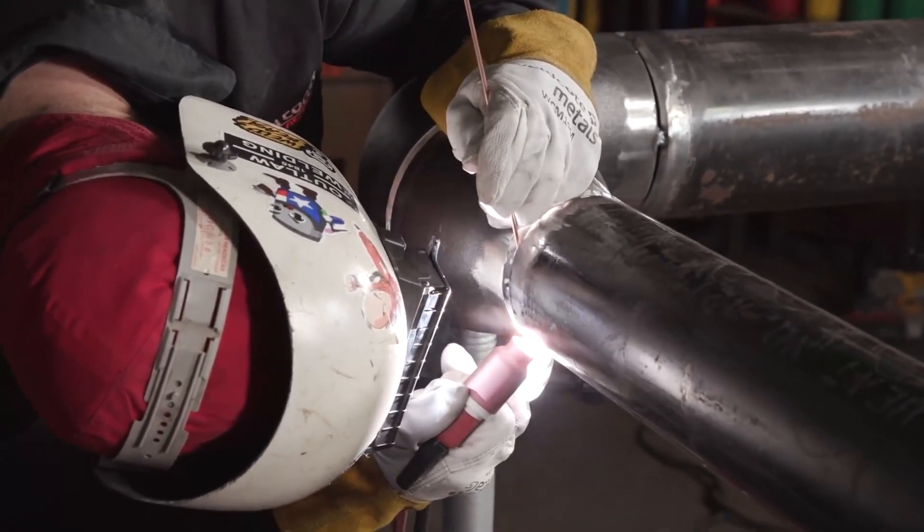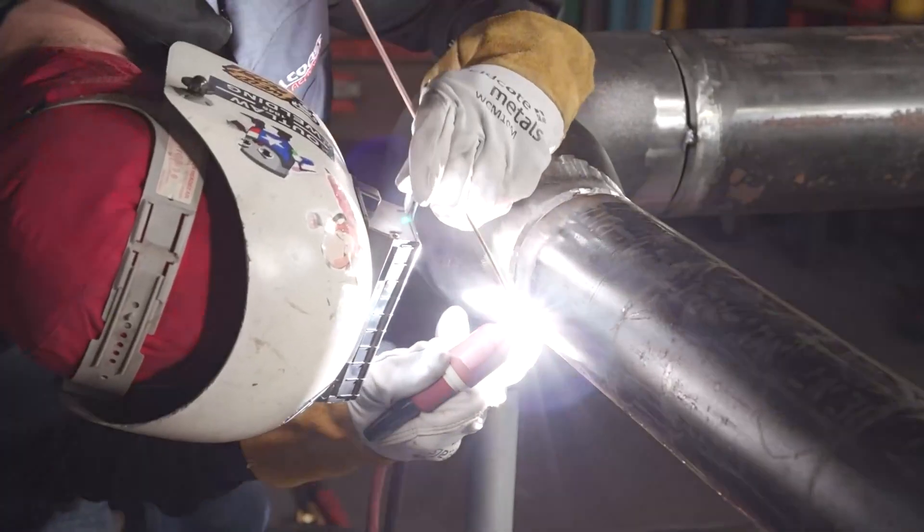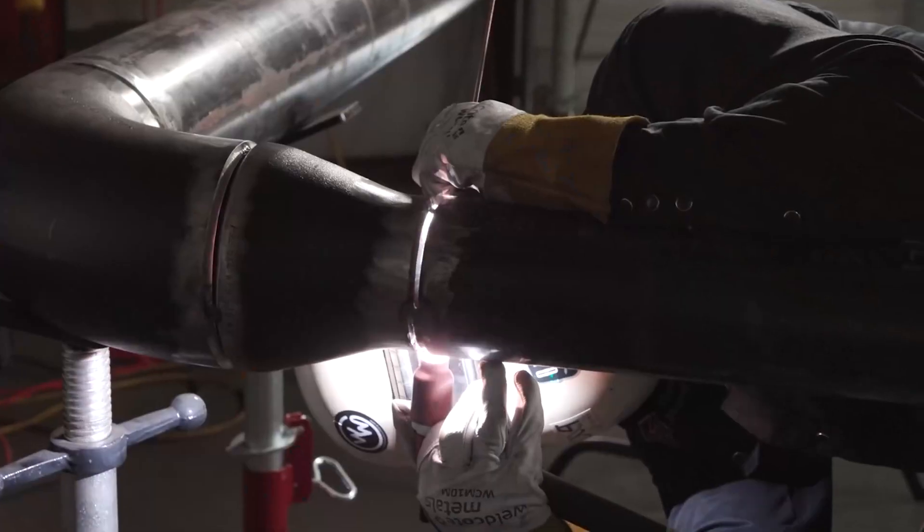The biggest one — number one — is safety. If we're talking about PPRCT versus steel, you're welding both of them, but they're different types of welding. With PPRCT you have fusion welding, and with steel you have welding with open flame, fire watch, and things like that — much different from fusion welding PPRCT, where you don't have open flame, just heat. Not only is that a safety benefit, it's more productive because you don't have to have an extra standby on fire watch, you don't need a burn permit, and you don't have to set up safety welding curtains on an open job site. There's also a material side: more consistent pricing in the market with PPRCT as opposed to metallic systems.